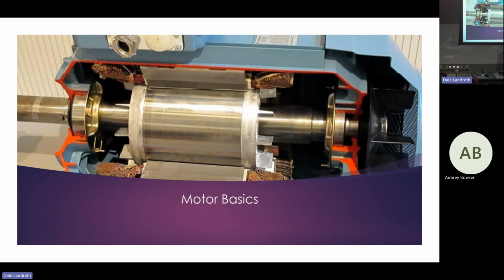Exactly, we never meg a motor in a deep vacuum. By deep vacuum, there's a Trane centrifugal in a vacuum. It's in a vacuum, but it has refrigerant and such, but it's not a deep vacuum. So if you're evacuating a chiller and you got it down to 30 inches - everybody knows I'm just saying this, we don't get it down to 30 inches, but you know what I mean - and you meg a motor, there's a possibility you can damage the motor. So don't ever do that. Let's be mindful of those things.